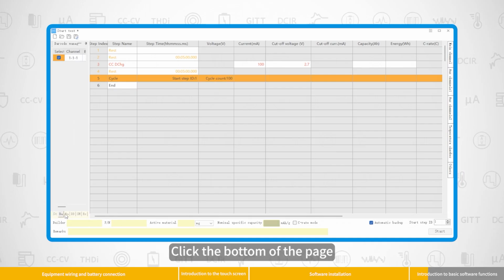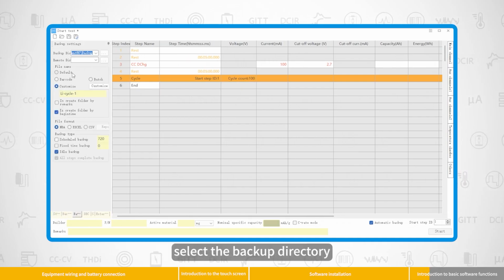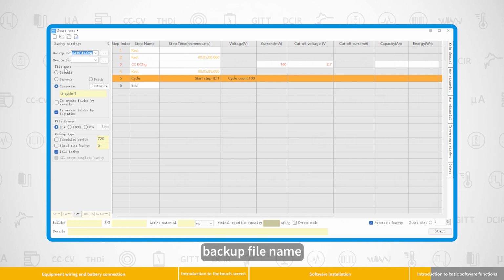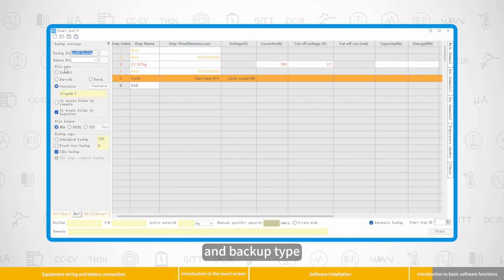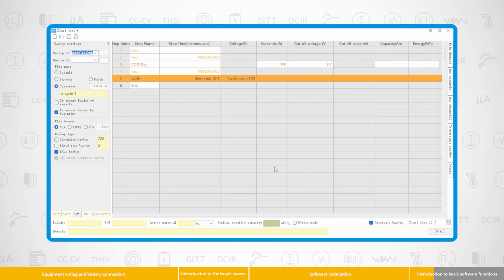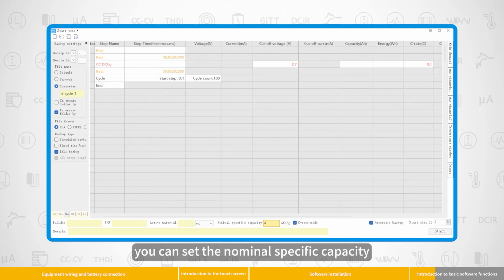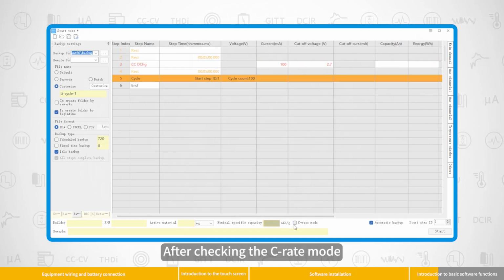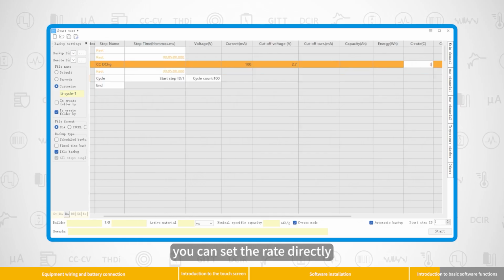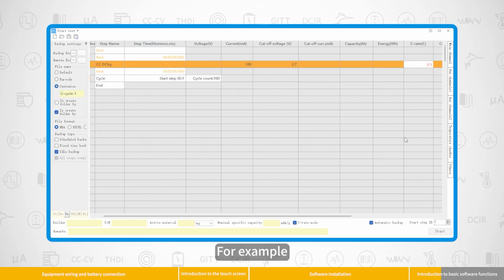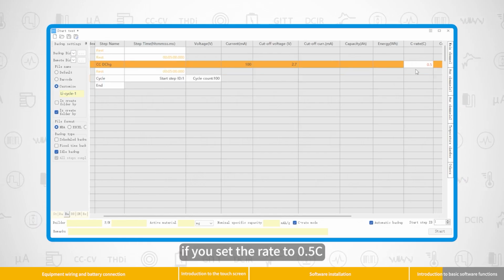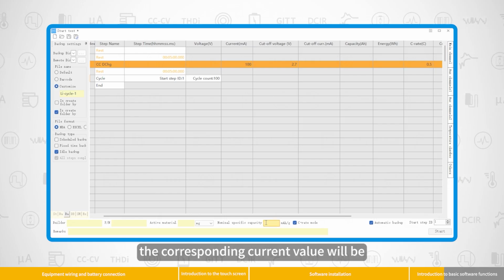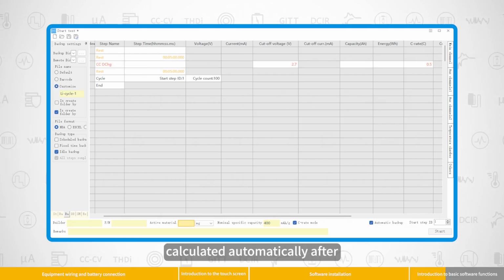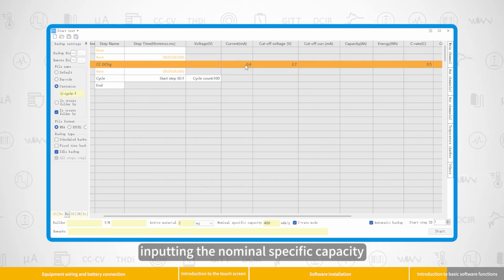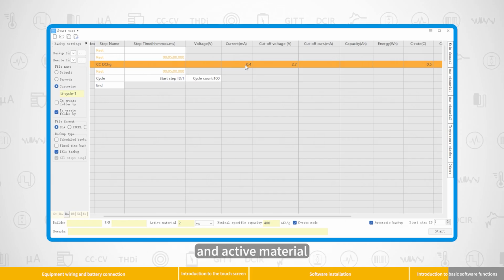Click the bottom of the page, you can set the backup settings, select the backup directory, backup file name, backup format and backup type, etc. At the bottom of the page, you can set the nominal specific capacity and active material. After checking the C-rate mode, you can set the rate directly. For example, if you set the rate to 0.5 C, the corresponding current value will be calculated automatically after inputting the nominal specific capacity and active material.